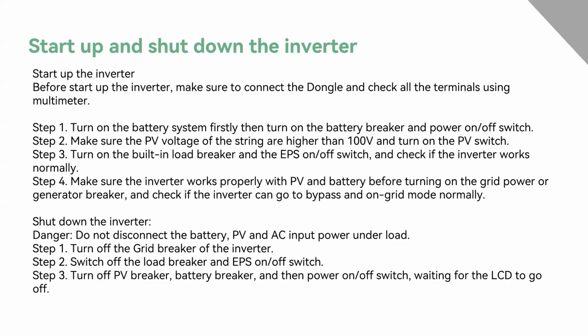After that, we can turn on the built-in load breakers and the EPS on switch, and then there will be power output on the EPS port, and we can check if the inverter works normally to supply power to the loads. And after that, make sure the inverter works normally with PV and batteries, and then we can turn on the grid power or the generator and check if the inverter can go to the bypass or on-grid mode normally to verify the whole system can work normally.